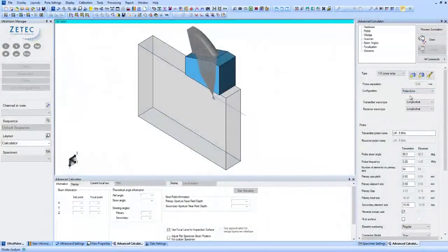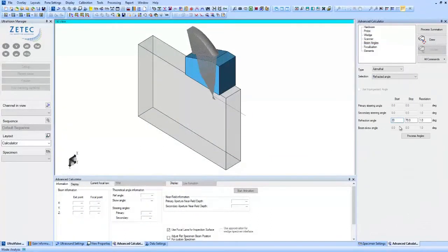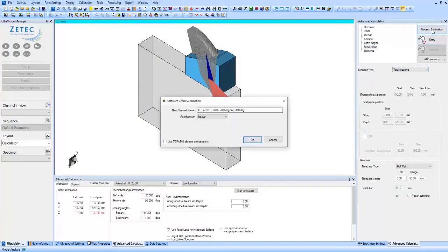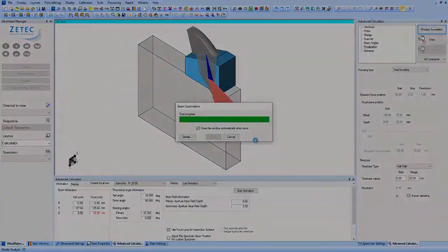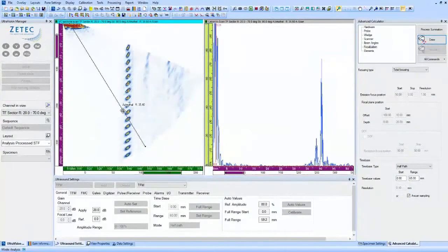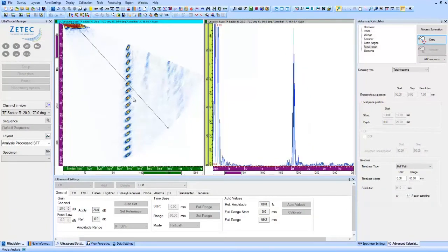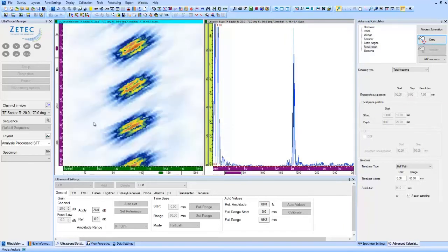It is also possible to reconstruct standard phased array data for any given focal law and for sectorial total focusing, both with very fine angular increments. Here we show the reconstructed sectorial total focusing channel with an angular increment of 0.2 degrees. In addition to the excellent focusing and the very fine resolution on the sector scan view, this algorithm generates an A-scan signal for each angle, just like standard phased array.